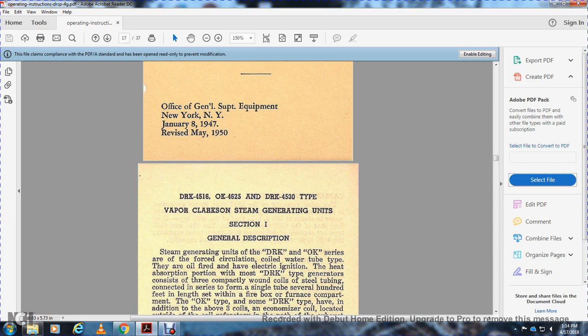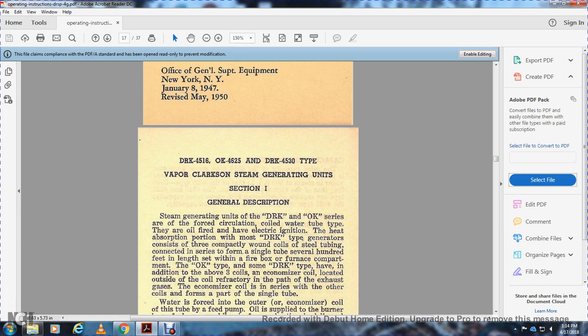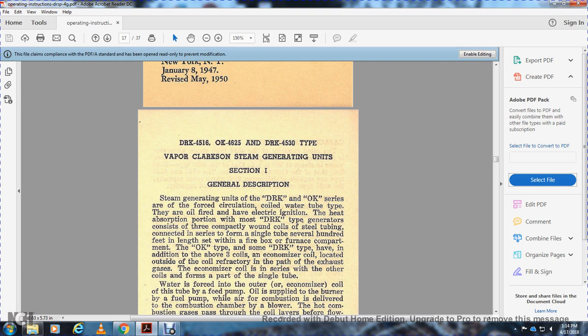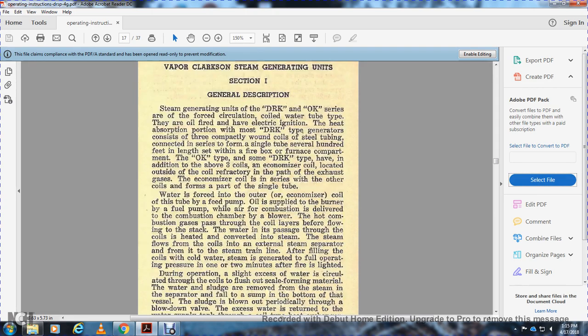Section 1, general description. The DRK 4516, OK 4625, and DRK 4530 type Vapor Clarkson steam generators in the DRK and OK series are forced circulation coil type, oil fired, with electrical ignition. The heat absorption portion of most of the DRK type generators consists of three compactly wound coils of steel tube connected in series, a single tube several hundred feet in length, set within a firebox furnace. Some of the DRK type have, in addition to the three coils, an economizer coil located outside of the coil refractory in the path of the exhaust gas. The economizer coil is set in series with the other coils and forms part of the single tube.